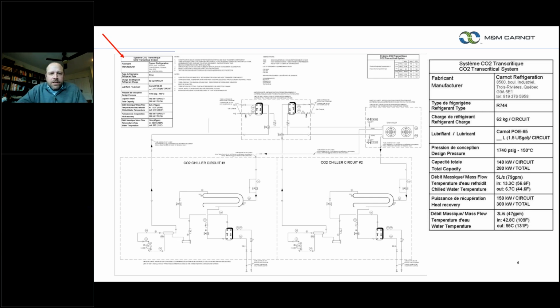Real quick, this is the piping schematic of this chiller. So this box right here is that chiller, located inside of the mechanical space. You have your compressor down here, which sends the hot gas to these heat exchangers. These heat exchangers basically decide if the building needs heat at the moment, and if it doesn't need heat, these valves close and send that hot gas up to a gas cooler located on the roof. So in wintertime operation, instead of rejecting the heat to the atmosphere, you're rejecting it into this building's hot water loop. And that hot water loop in the building requires 131 degree water.